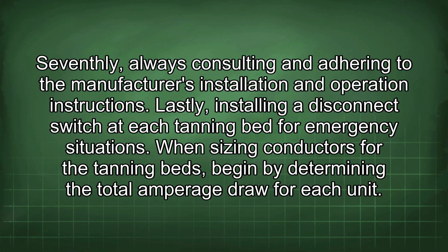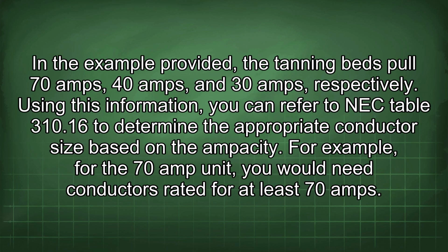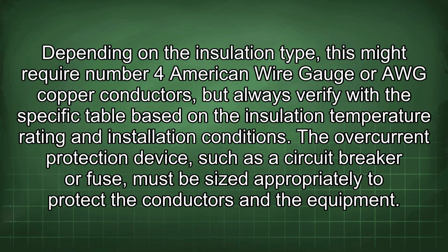When sizing conductors for the tanning beds, begin by determining the total amperage draw for each unit. In the example provided, the tanning beds pull 70 amps, 40 amps, and 30 amps, respectively. Using this information, you can refer to NEC Table 310.16 to determine the appropriate conductor size based on the ampacity. For example, for the 70 amp unit, you would need conductors rated for at least 70 amps. Depending on the insulation type, this might require number 4 American wire gauge or AWG copper conductors, but always verify with the specific table based on the insulation temperature rating and installation conditions.